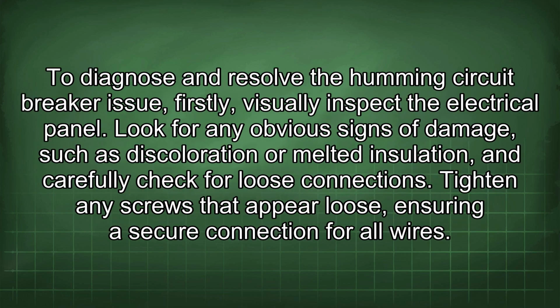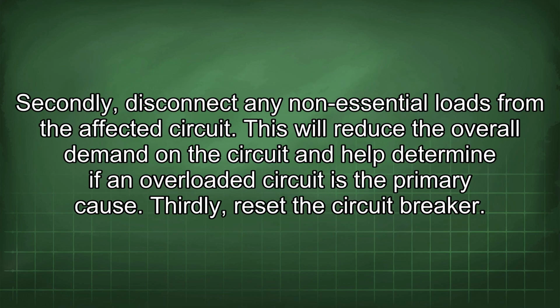To diagnose and resolve the humming circuit breaker issue, firstly, visually inspect the electrical panel. Look for any obvious signs of damage, such as discoloration or melted insulation, and carefully check for loose connections. Tighten any screws that appear loose, ensuring a secure connection for all wires. Secondly, disconnect any non-essential loads from the affected circuit. This will reduce the overall demand on the circuit and help determine if an overloaded circuit is the primary cause.